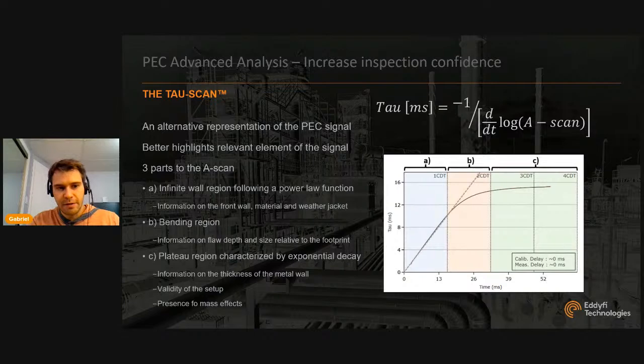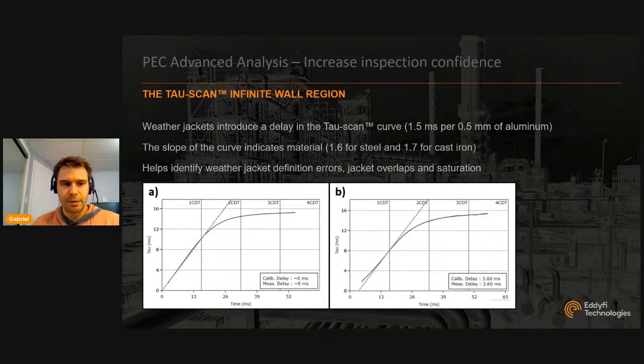There are three parts to the Tau scan, or to the A scan. First, in blue, there's an infinite wall region, where you see that the slope is constant. That provides information on the material that you're inspecting, whether it's cast iron or carbon steel, as well as the weather jacket. Then there's the bending region, the second region of the Tau scan, which provides information on flaw depth, as well as the size of the flaw relative to the probe's averaging area or footprint. And then there's a plateau region that's characterized by an exponential decay, the nearly constant slope that you'll see in our A-scan representation. That provides information on the thickness of the material, the validity of the setup, the presence of mass effects, noise, things like that.